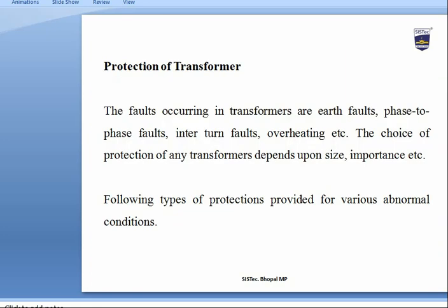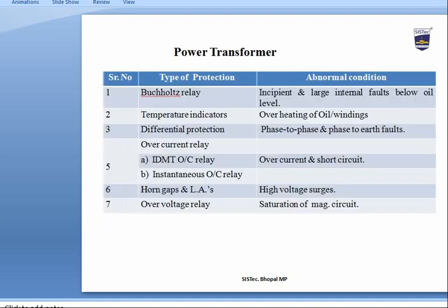Faults occurring in transformers include earth faults, phase-to-phase faults, inter-turn faults, and overheating. The choice of protection depends upon the size and importance of the transformer. For power transformers located in power plants, the Buchholz relay is used for incipient and large internal faults below oil level.